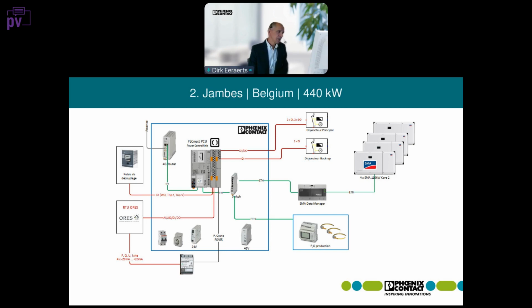And then from here we send the control signals out to the plant in the field, and we have in the field switchgear, a main switch and a backup switch, where we have to read the statuses but also send control signals if we are asked to do so. And then we have the inverters, which in this case we can connect to through a data manager supplied by the same manufacturer. This can be the case, it's not always the case. We can perfectly well communicate directly with the inverters on the right hand side. So this is the standard setup.